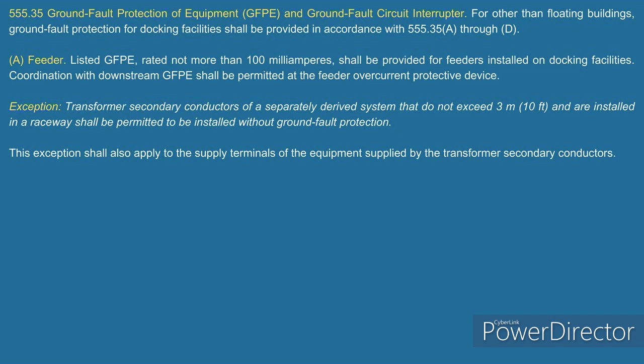He's making a blanket statement that anywhere that you just pick up current, that's an outlet. That's not correct. I've been saying this over and over. And this particular section here that we're dealing with, that deals with the ground fault protection of equipment and GFCI for personnel protection, they've got them separated here, and they're specifically calling out receptacles. And the reason they are is because a receptacle is a device where it's receiving its current, but the receptacle outlet is the box. That's where the outlet is. It's not the receptacle; it's the outlet box, and that's where your cord and plug connect.